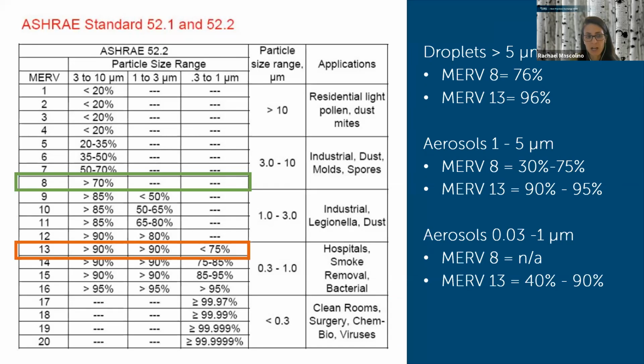To date, we still do not have contact tracing examples of the virus being transmitted through an HVAC system from one zone to another. So there's a lot of fear of, if I'm in one office area and there's a return air duct back to an air handler and that air is being mixed with other ventilation air through a set of mixed air filters and distributed back into another zone, it doesn't matter where I am in the building, the virus could still be transmitted, and that's not the case. And I think it's the combination of the filters that are replaced, even if they're only MERV 8, and that dilution with the ventilation air that's being drawn into those air handling units between different zones.